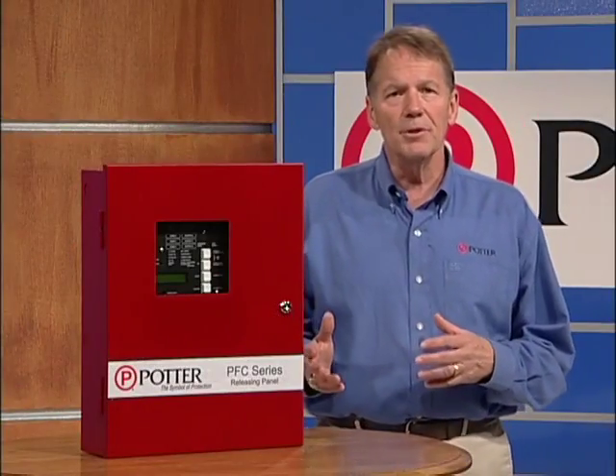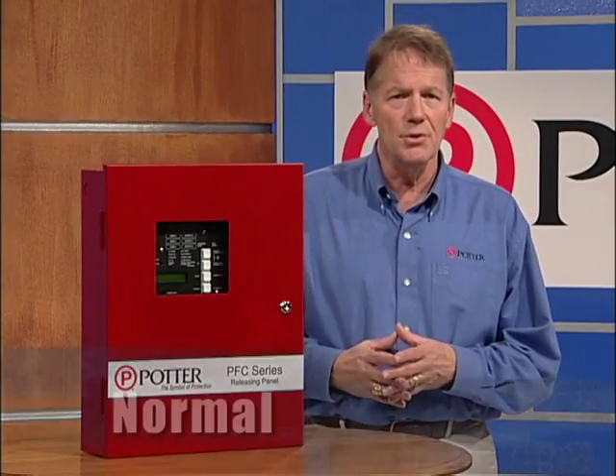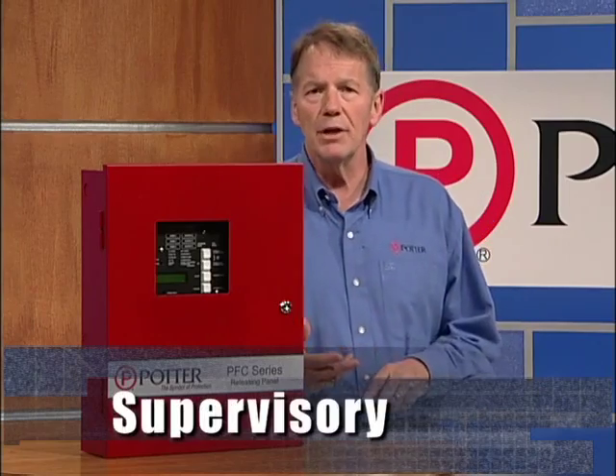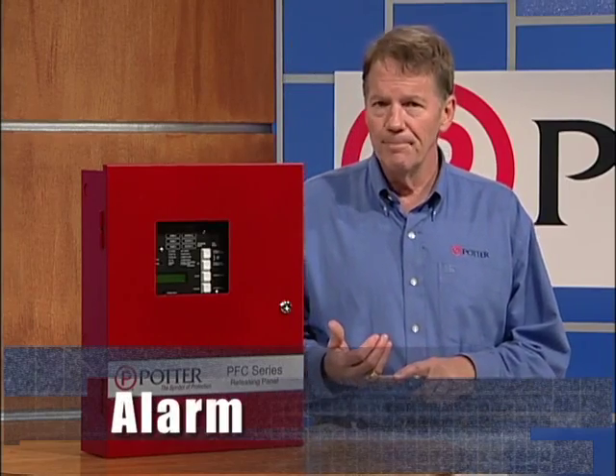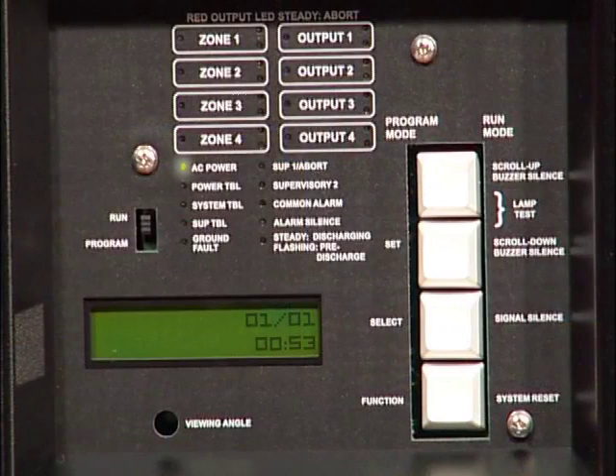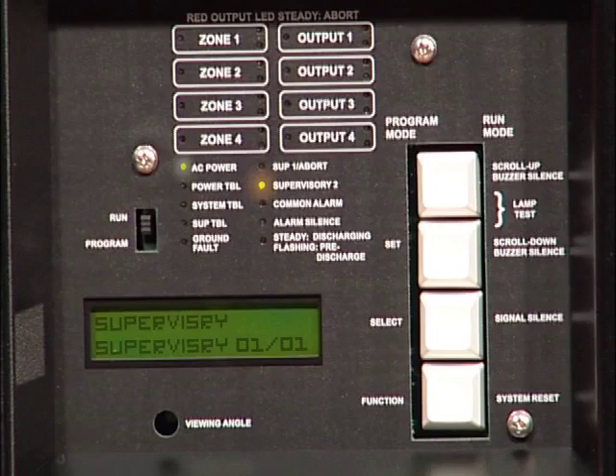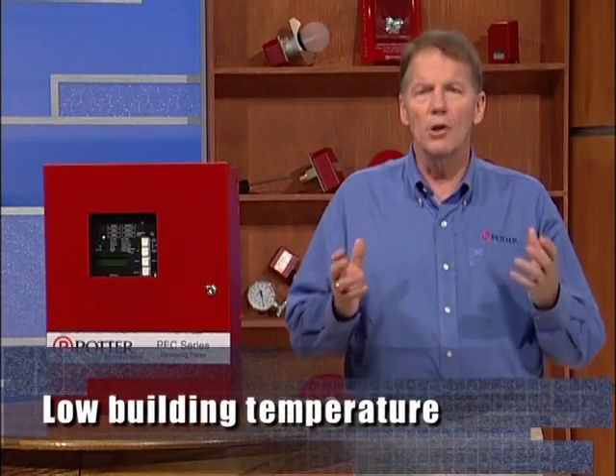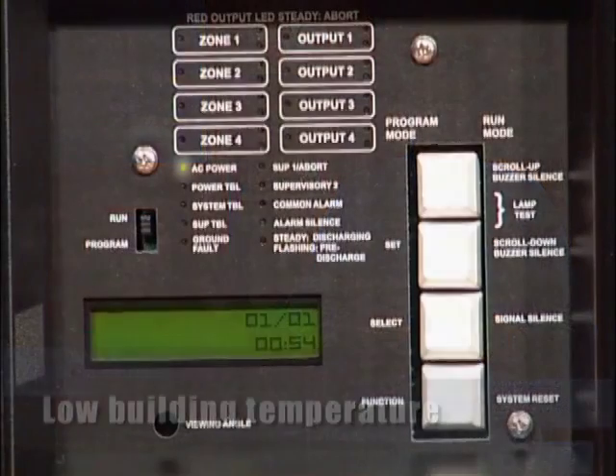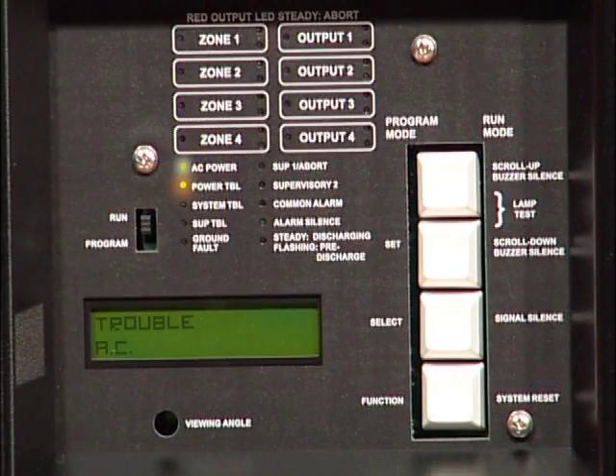The releasing panel displays 4 status conditions: normal, supervisory, trouble, and alarm. The normal status indicates the system is operating properly. The supervisory signal to the releasing panel indicates an off-normal condition. When a supervisory signal is triggered, a situation exists that needs to be checked out.